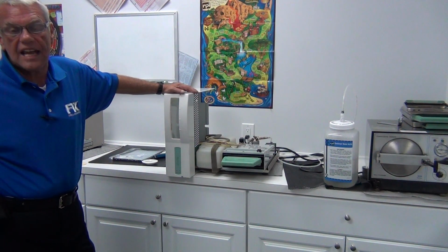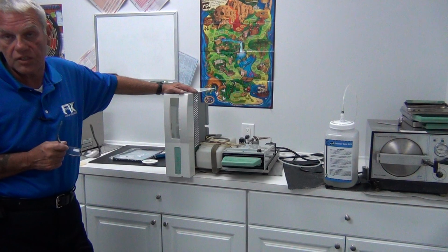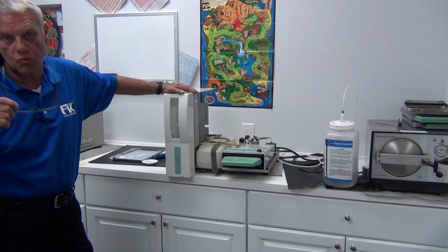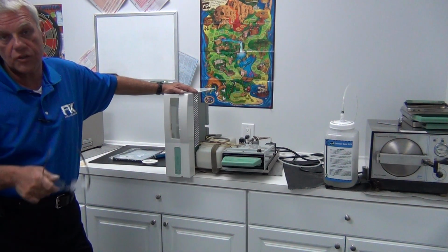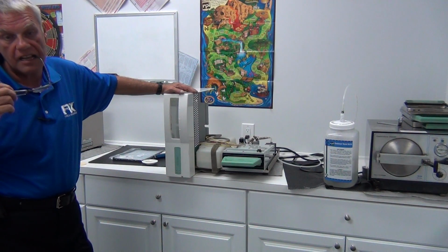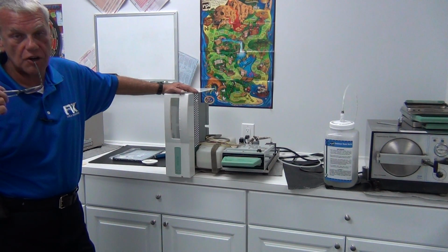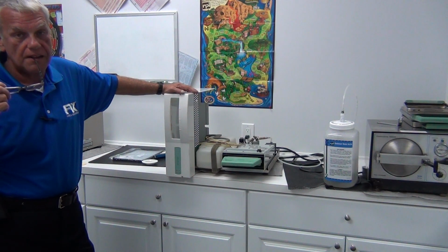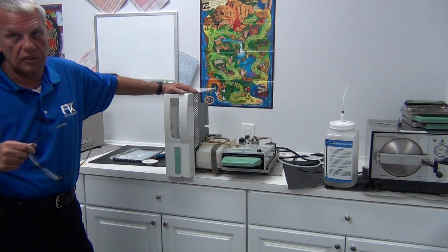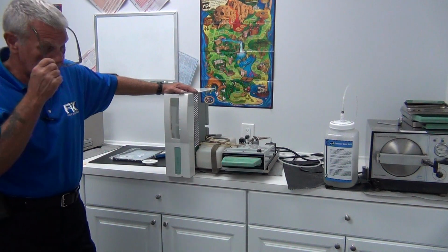By the way, Statims do not dry as quick as the bigger sterilizers. Statim allows 1 hour air dry. And the more you pack the cassette, the more it takes to dry that cassette out. Now, it's very important not to overload a cassette in the Statim sterilizer.